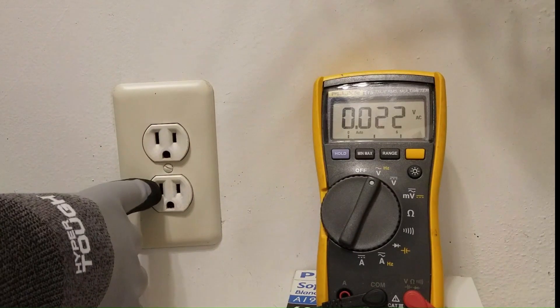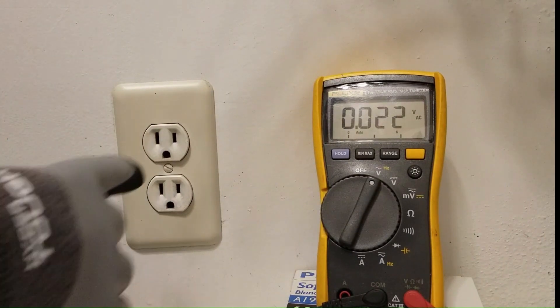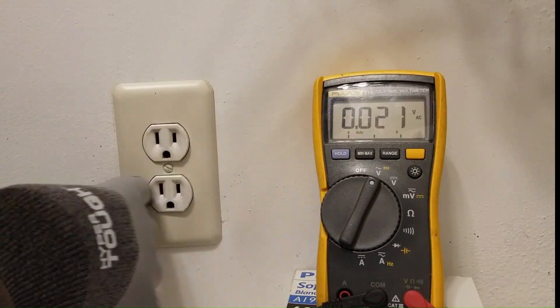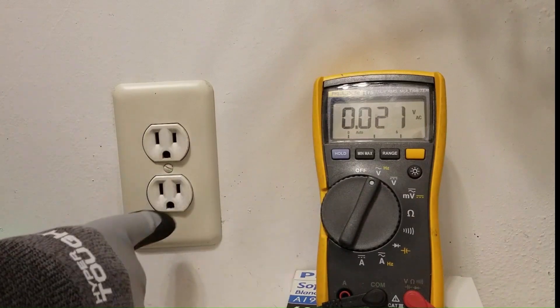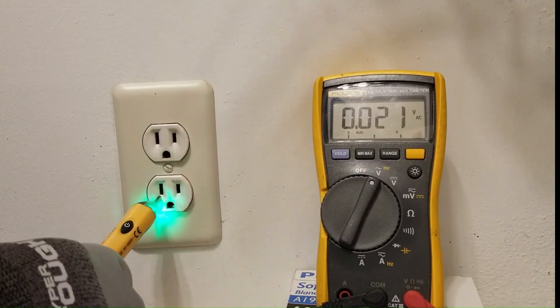What happens is when neutral floats and you put a load in here and you only have a couple of volts difference between the two, by definition neutral is going to be up close to 120 volts.